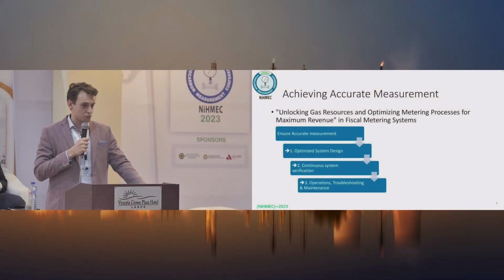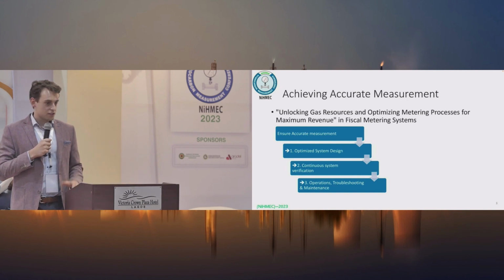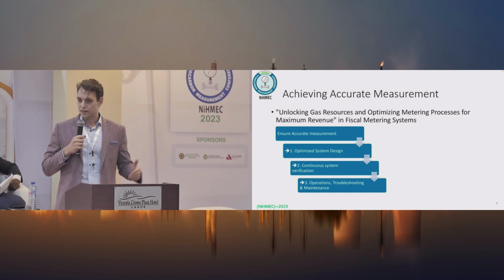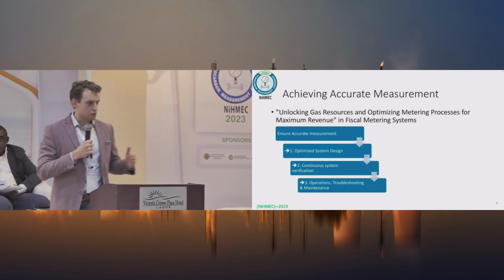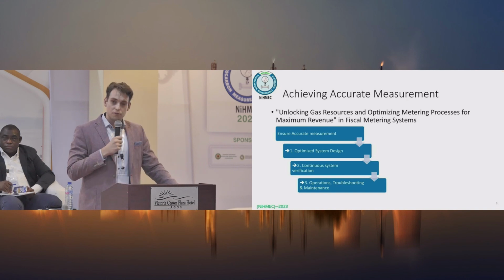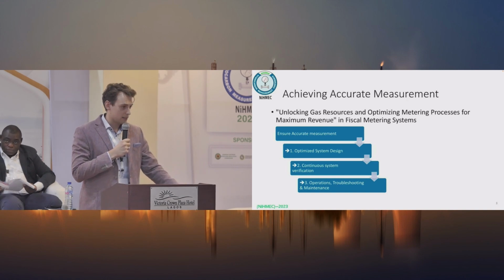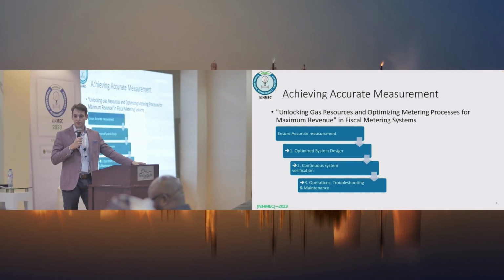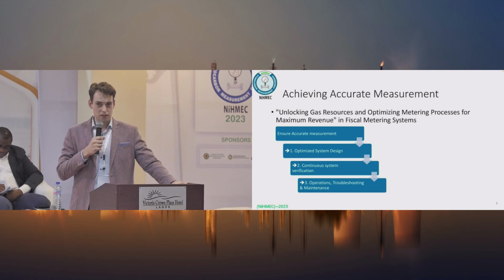In order to unlock gas resources and optimize metering processes, we need accurate measurement. First, we ensure the metering systems we install and operate are accurate. This requires an optimized design, because if the application isn't a right fit for the metering system, it won't work well. Second, once installed in the field, we need continuous verification that instruments are still operating correctly. Lastly, we need correct operational, troubleshooting and maintenance procedures in place, because improper maintenance and operation can introduce mismeasurements.